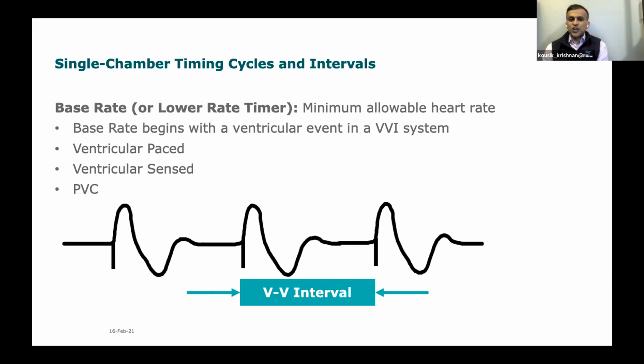So a single chamber system is probably the easiest to understand the timing cycle because it's just one lead. It doesn't have another chamber that it needs to sense off of or sync to. So we set a lower rate limit, which is also a lower rate timer. The easiest one to remember is 60 beats per minute. That tends to be a conventional lower rate limit. It happens to be 1 beat per second, and 1 second is 1,000 milliseconds.